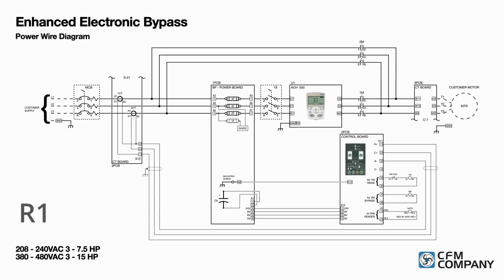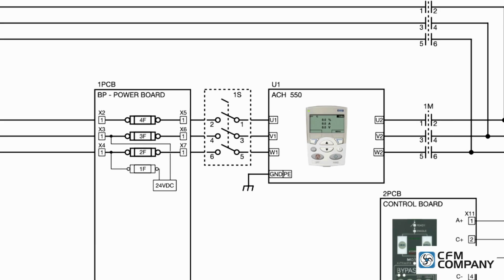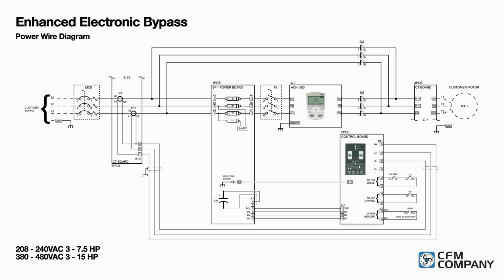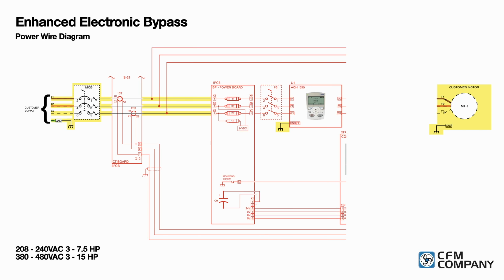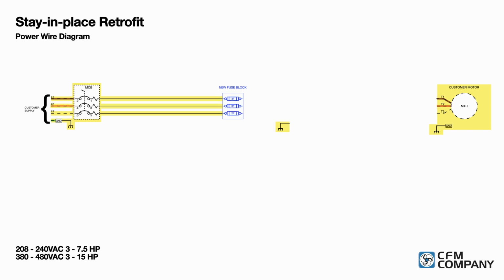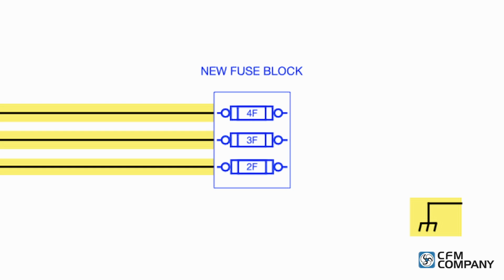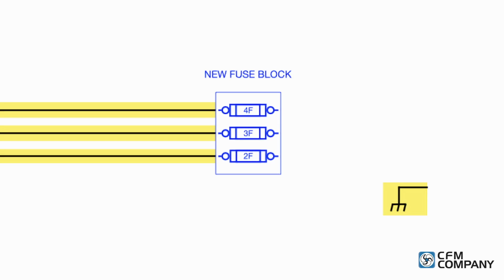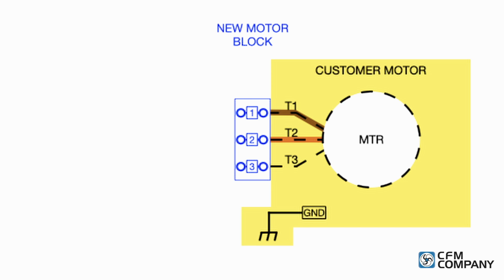removed. For the R1 and R2 stay-in-place bypass replacement, only the main circuit breaker or main disconnect can be reused. For these frame sizes, the fuse block and the motor terminal block are integrated into the printed circuit boards that will be removed. A new fuse block will need to be installed. Fuses with the original amp rating and fuse type should be used. The original fuses can be reused if they are good. And a new motor terminal block will need to be installed.